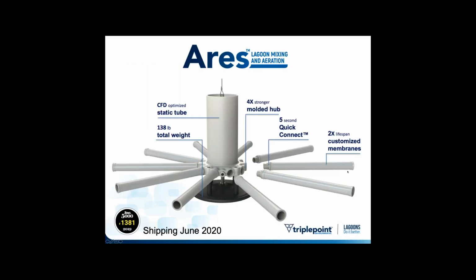So just briefly, some features for you of the unit. A couple things that I'll highlight. One is that we reduced the weight, as I mentioned, and we did that by moving to a cast iron ballast. And what cast iron does is it actually has a higher density than concrete, which is what the typical ballast material is. So you need less weight to weigh the unit down and keep it ballasted on the bottom. But it's actually heavier in the water, pound for pound, than concrete. So we were able to reduce weight while also increasing our safety factor when it comes to the overall ballast, which is really cool.